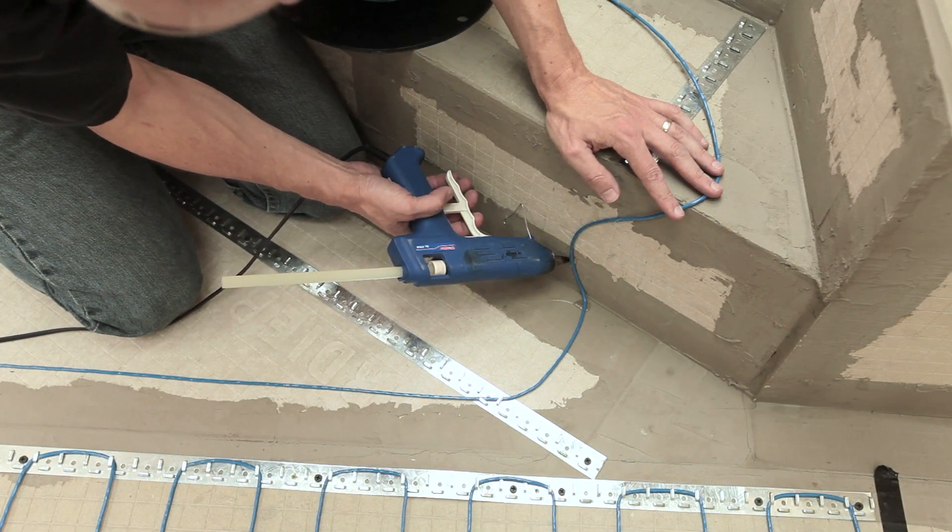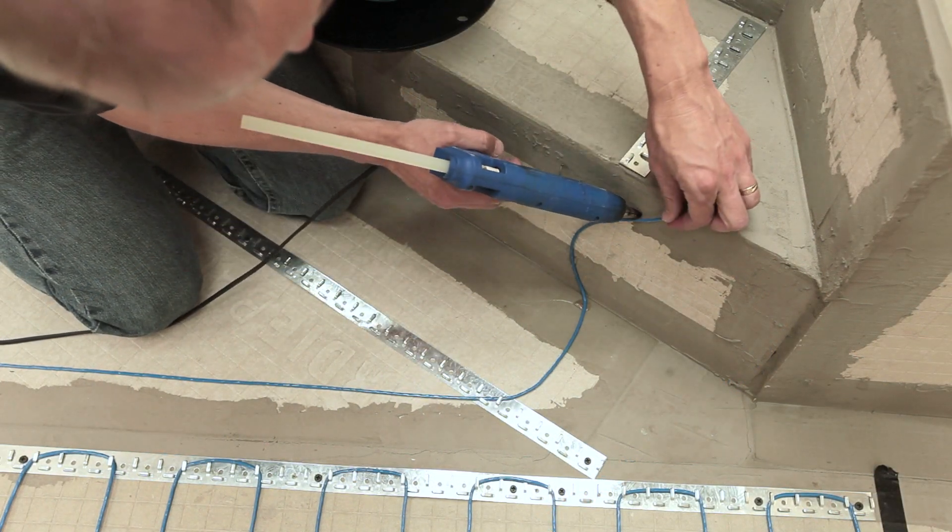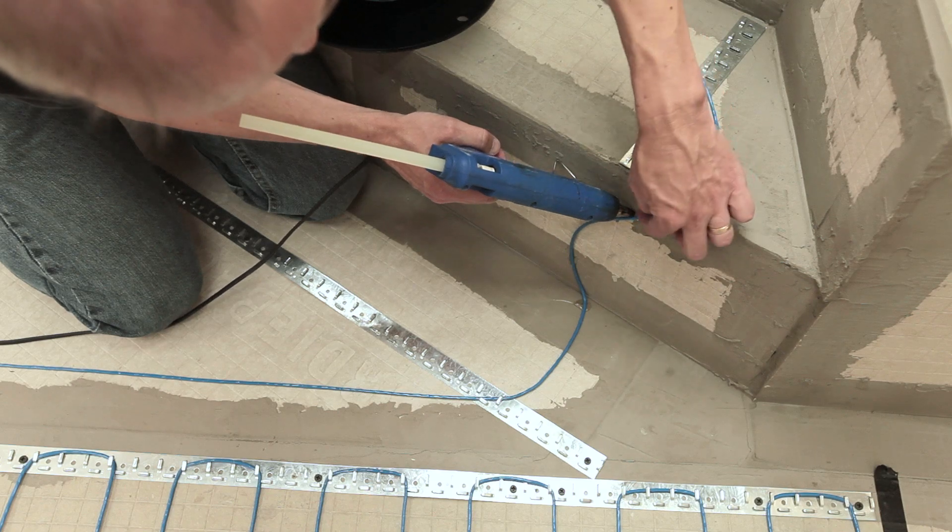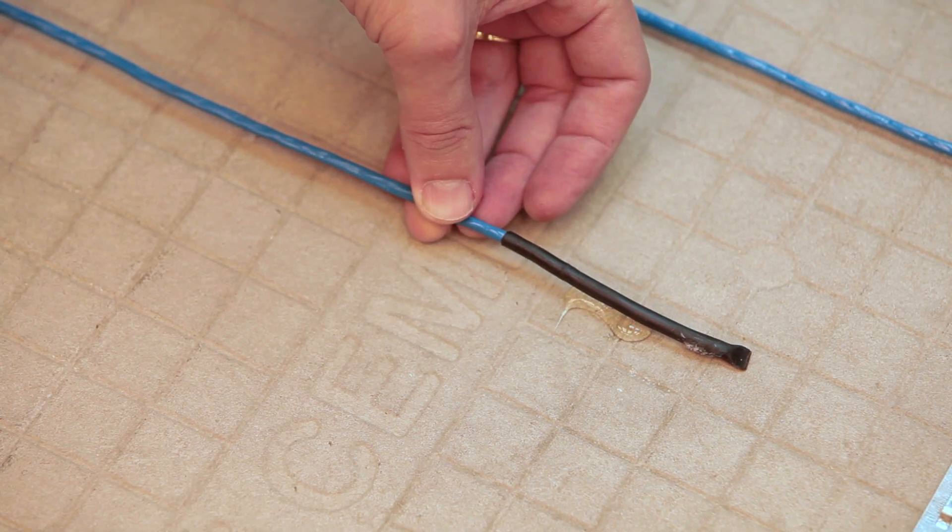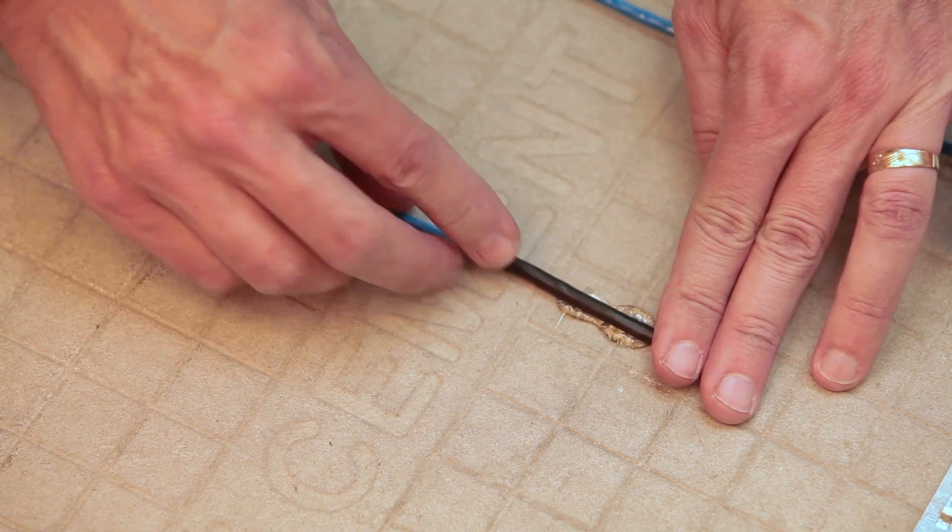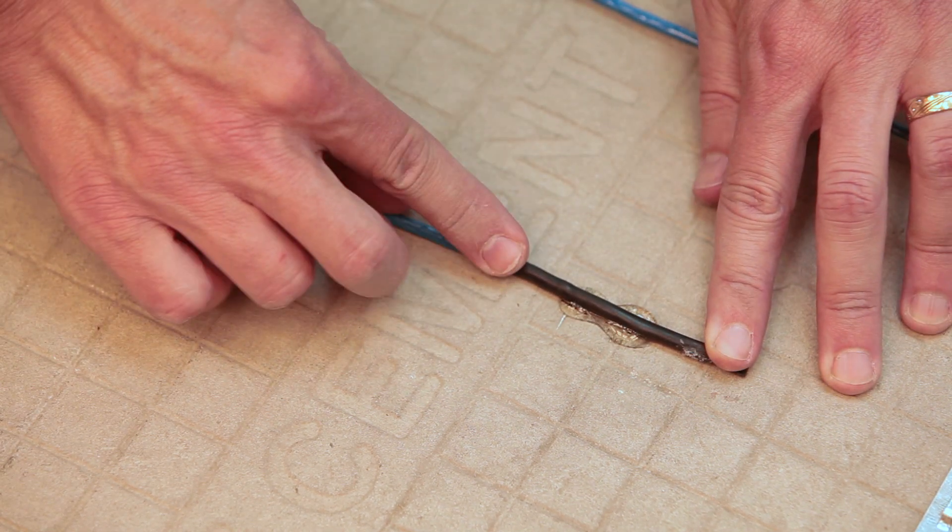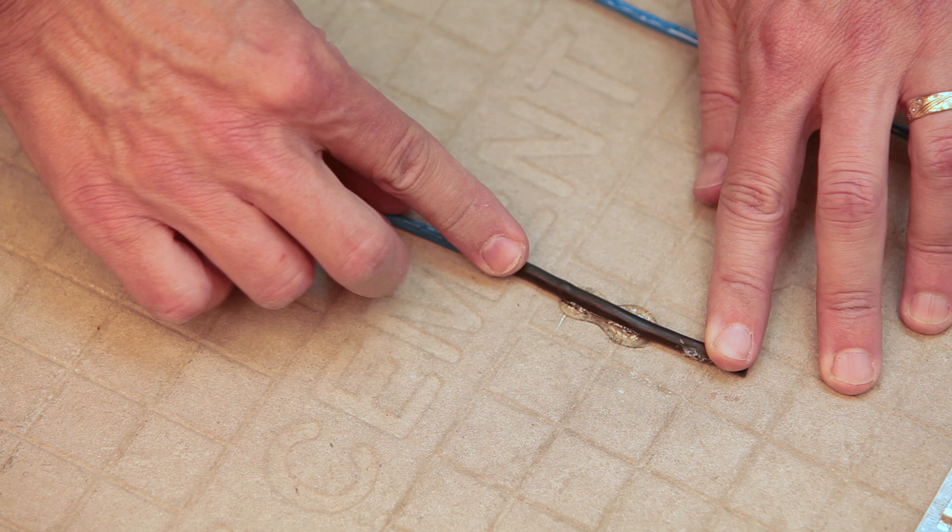In areas where warm wire changes direction without straps, hot glue can be applied to the floor surface to provide attachment. Once the end of the heating wire has been reached, attach the end splice to the floor with hot glue. Once again, it may be necessary to chisel out a portion of the floor depending on the thickness of the mortar used.